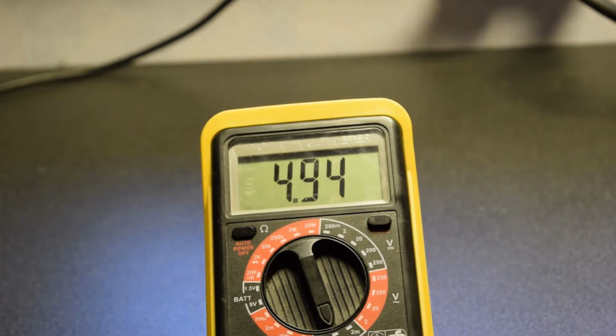Now we're going to test it under load. I'm going to draw an arc across the output and see how much current it takes. It looks like we're going to about 20 amps, so that's going to be my estimate. The power meter doesn't go beyond 20 amps because it just gives an overload screen. But 20 amps, and probably more if you keep it running.